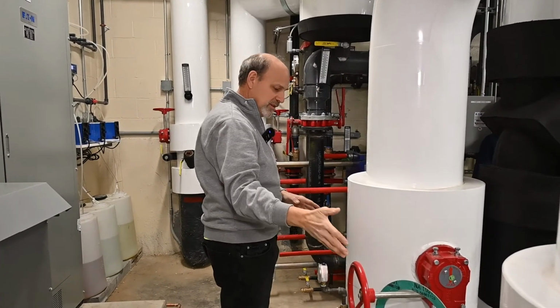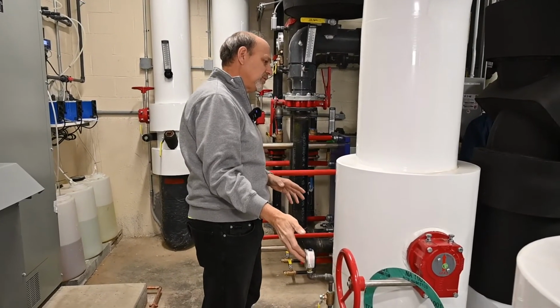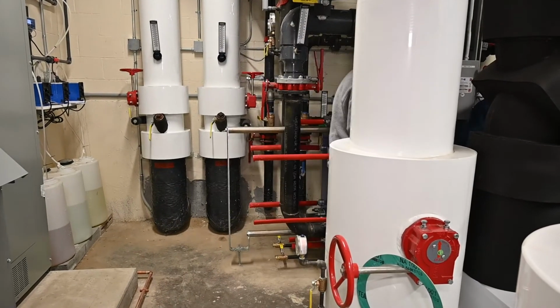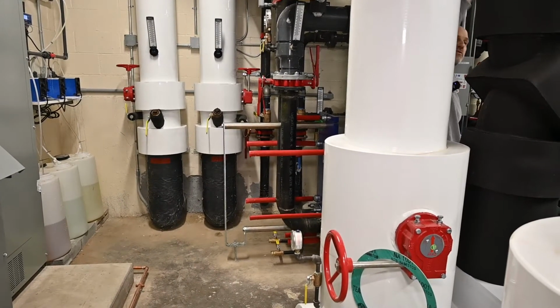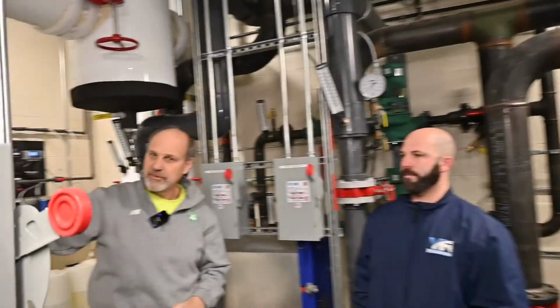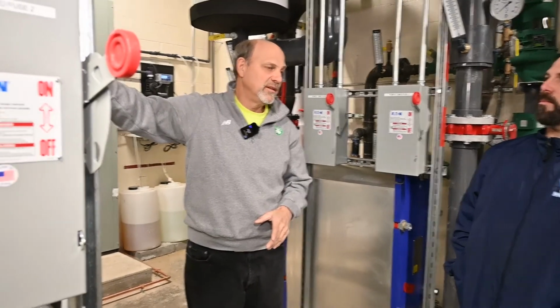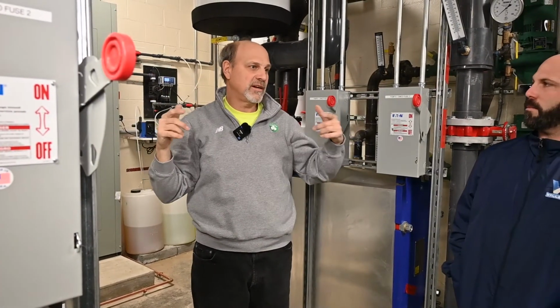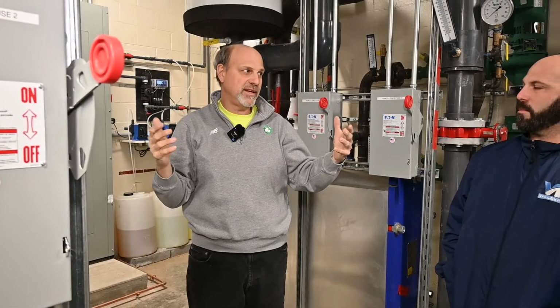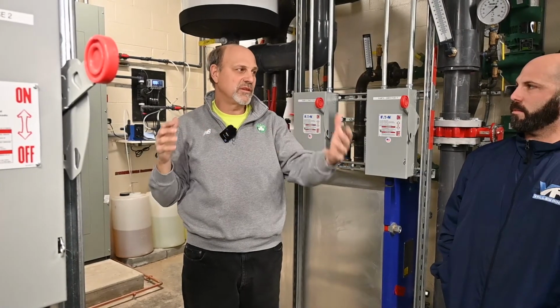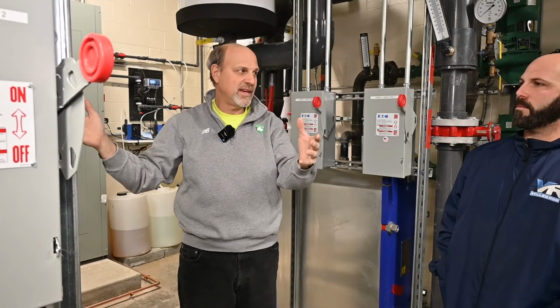You've got shut-off valves here, pressure gauges here on the pumps. Goes through the pumps, comes up off the discharge. This is a balancing valve. It's called a triple duty valve. It's actually a shut-off valve, a check valve, and a balancing valve. So any of these valves that you see in here, Carl has already pretty much balanced these valves as part of his commissioning process. It's not a set and forget type thing.